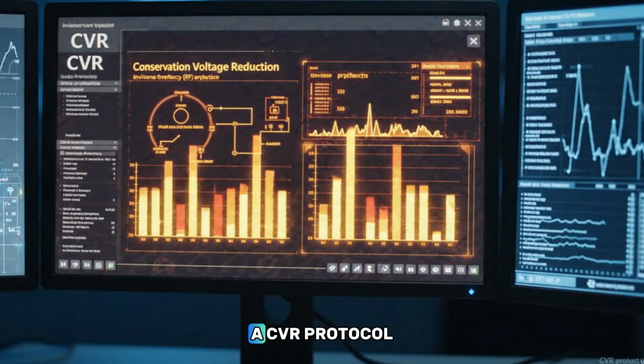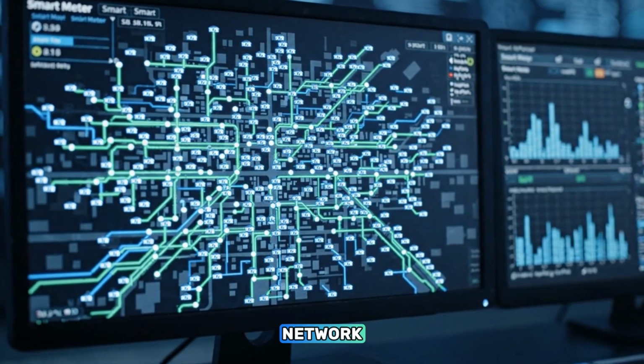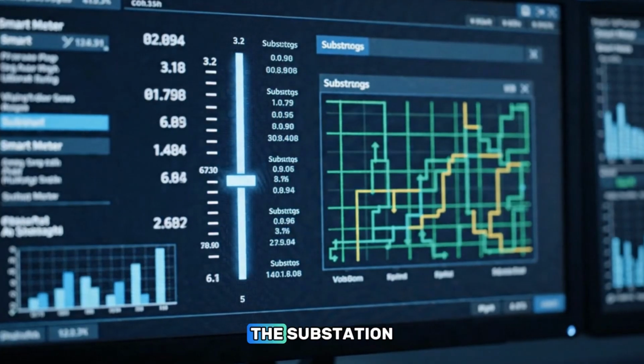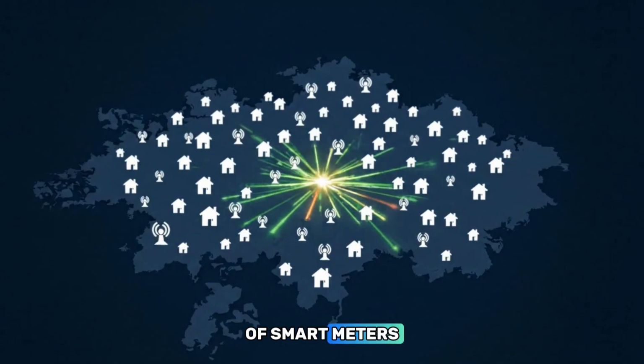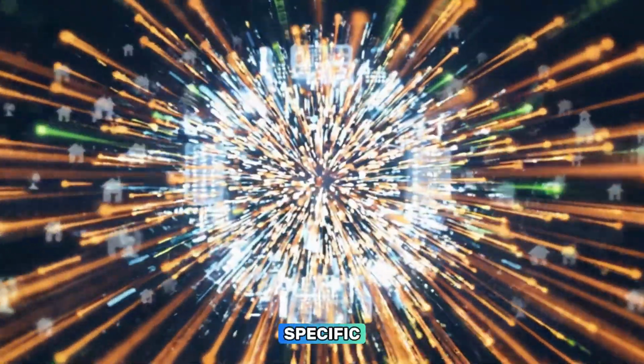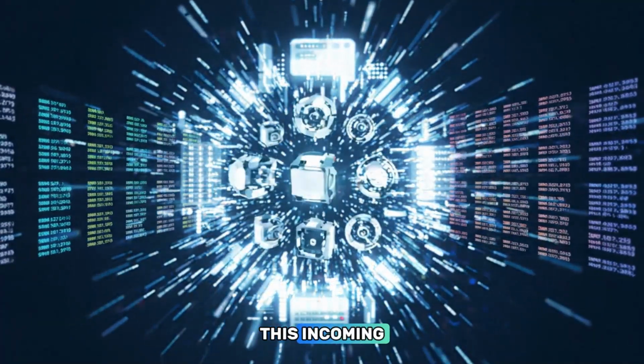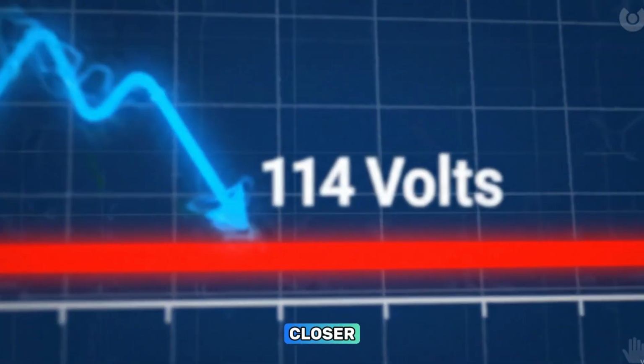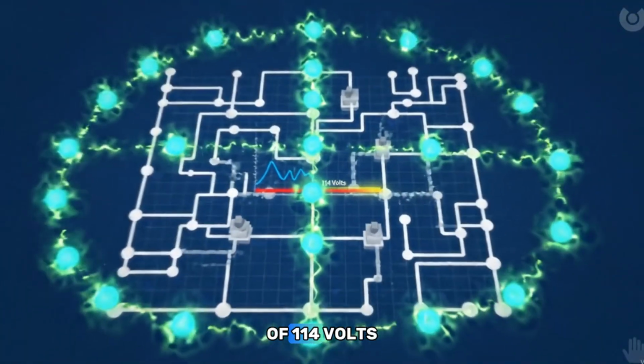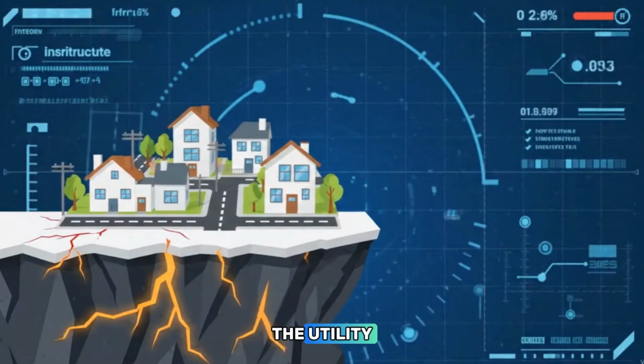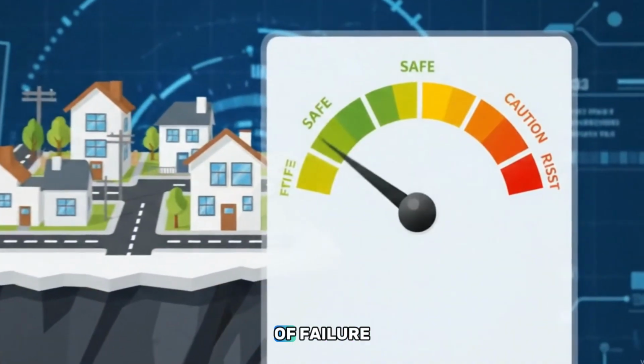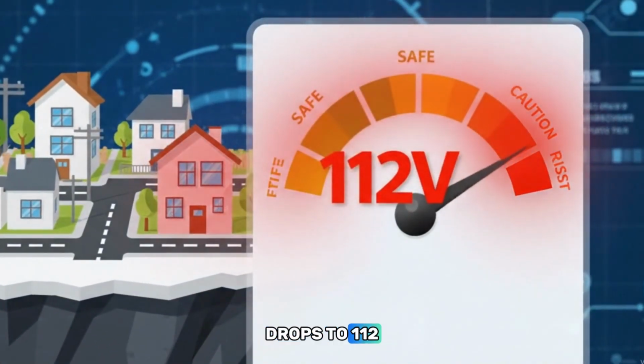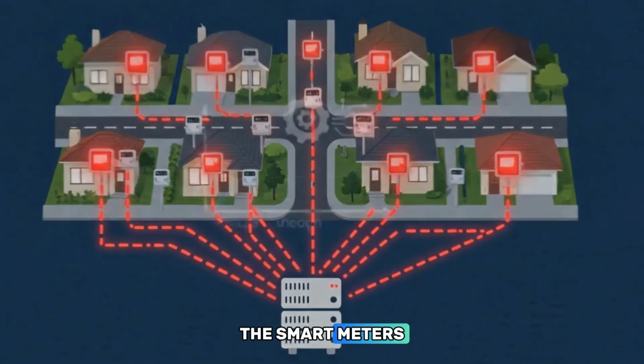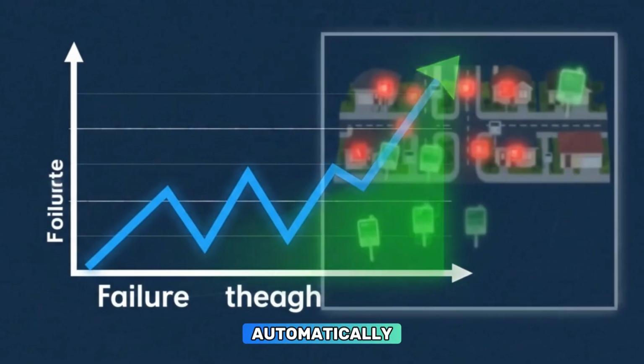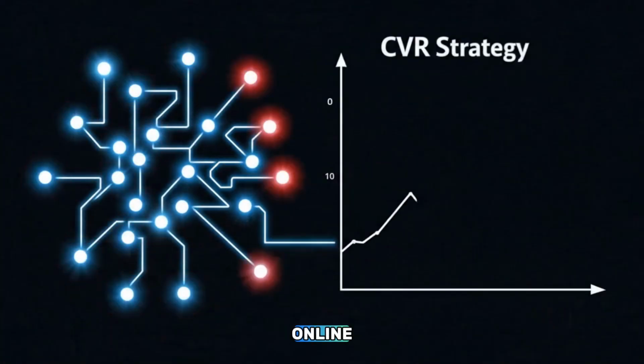When a grid operator initiates a CVR protocol, they use the smart meter network as their eyes. They slowly dial down the voltage at the substation. Instantly, thousands of smart meters report the precise voltage drop at their specific locations. The algorithms analyze this incoming data stream. They watch the voltage dip closer and closer to the legal minimum of 114 volts. The smart meter network allows the utility to push the neighborhood right to the absolute razor's edge of failure. If one specific street drops to 112 volts and risks a total blackout, the smart meters instantly flag the anomaly, and the algorithm automatically bumps the voltage back up just enough to keep the grid online. Without the smart meter network, aggressive CVR is impossible.